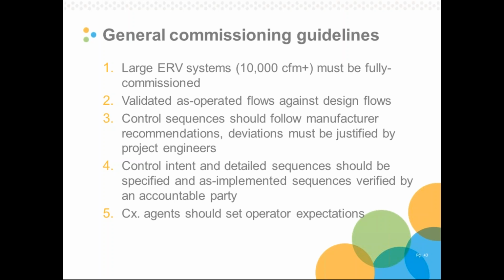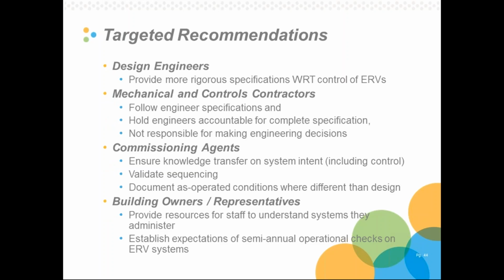The control intent has to be established as well as the detailed sequences. They should be specified, and if they have to change, the as-implemented sequences should be checked against our design intent and then verified by a commissioning agent or accountable party. And then lastly, there's got to be this knowledge transfer, and a big part of that is commissioning agents giving expectations to operators and building owners about what their energy recovery systems should be doing. These energy recovery systems should be on during specific times, off during specific times. There should be some basic way for us to assess whether they're on or off, and that's how we're going to guarantee savings.